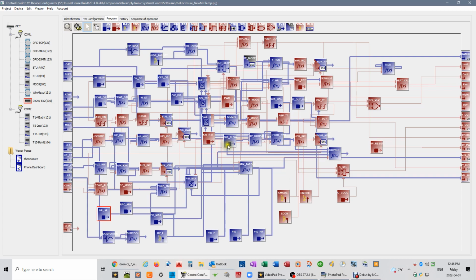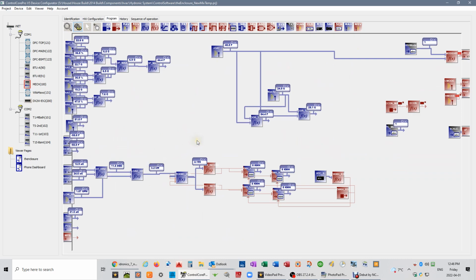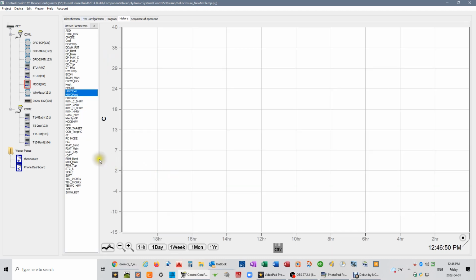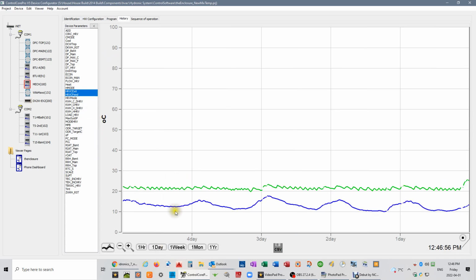So I think the last thing I'll quickly show you here is the performance of the HRV module. And so if we go to history, that's probably the easiest way to look at it. And we look at it over the week. The blue line represents the temperature feeding into the HRV module. So again, this was a module that is preheating the air, so it has conditioned water going to it. That is then being fed into the centralized mechanical ventilation system.